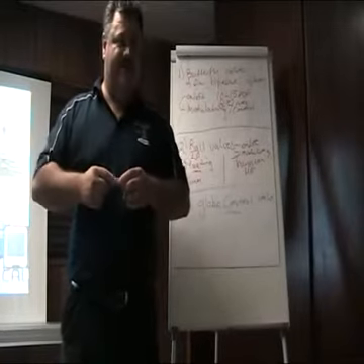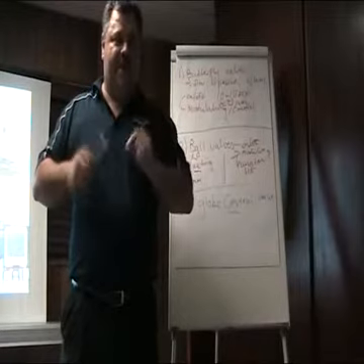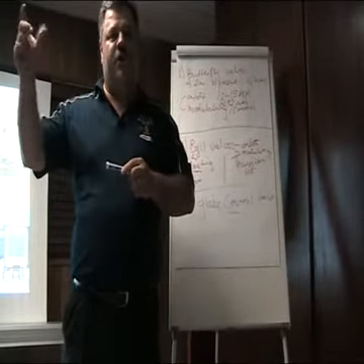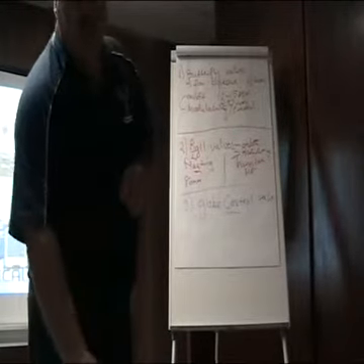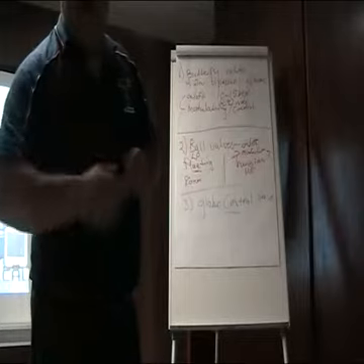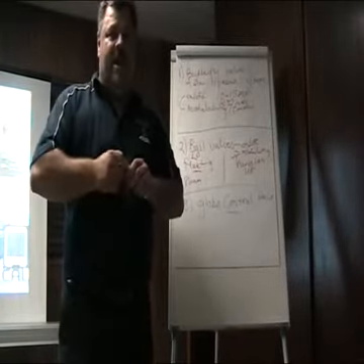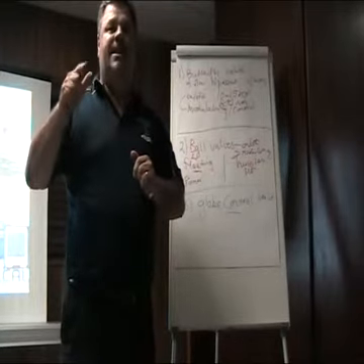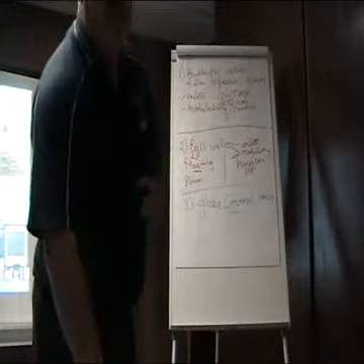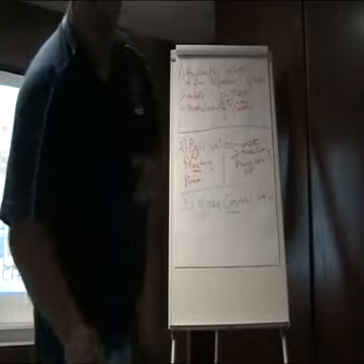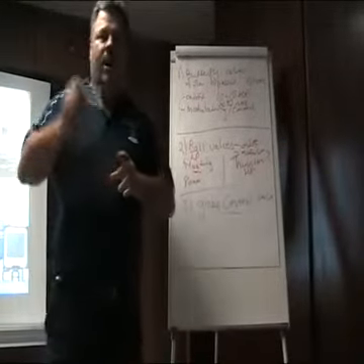It's because it's the most precise valve to control your application with. So if you've got an offset on your controller, I don't want to talk proportional, integral, derivative. If you want precise control, if you want your process to get the least upset, if you want your process to get to the set point the quickest, this is the type of valve that you would use. Globe valve. Because you can do magic with your trim.